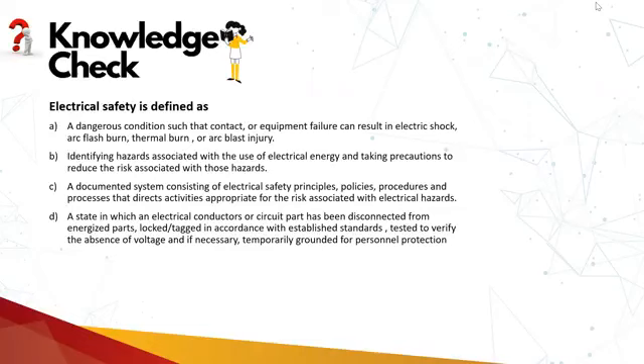A state in which an electrical conductor or circuit part has been disconnected from the energized part, locked and tagged in accordance with the established standard, tested to verify the absence of voltage if necessary, and temporarily grounded for personal protection. This is, I guess, the electrically safe condition. Yep. Establishing an electrically safe work condition. Jazib has also put it right. This is the definition of electrically safe work condition. ESWC, electrically safe work condition.